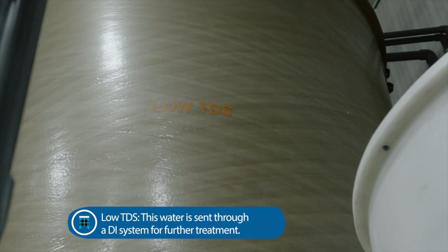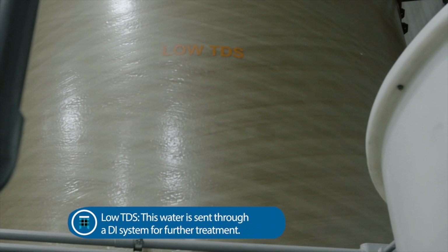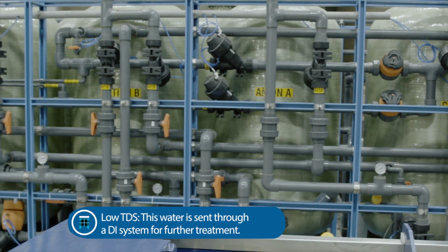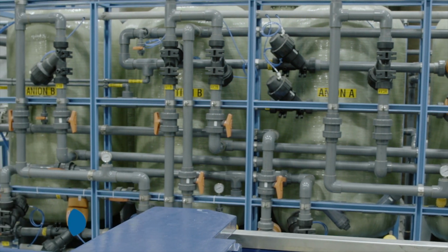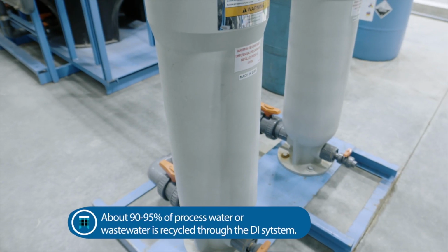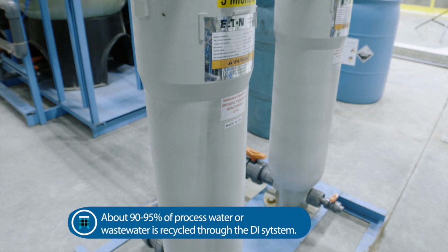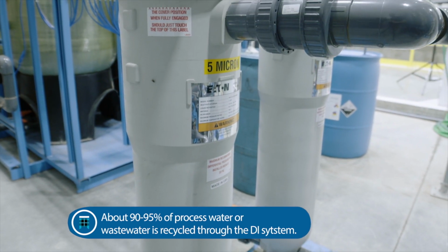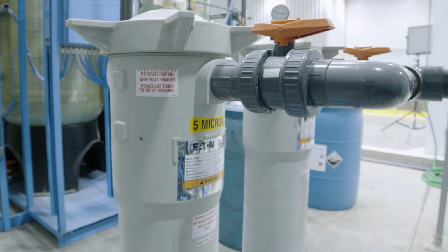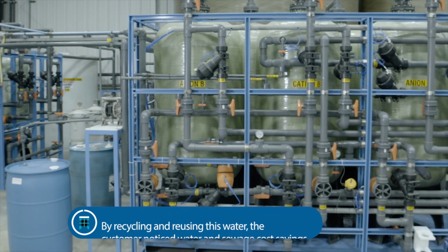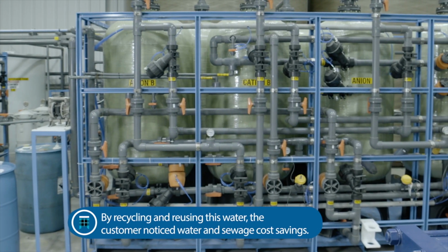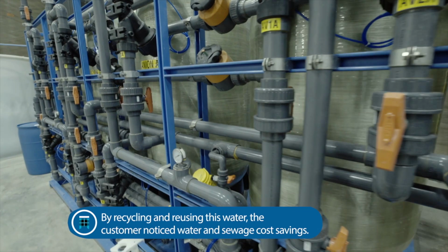Low solid wastes are sent through a DI system for treatment and recycling. Around 90 to 95% of this wastewater is recycled through our DI system. By reusing this water, the customer achieves both water and disposal cost savings.